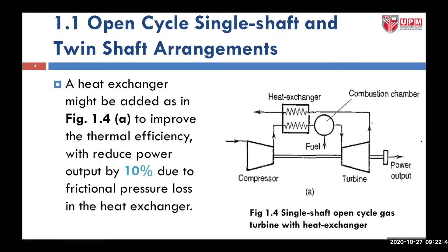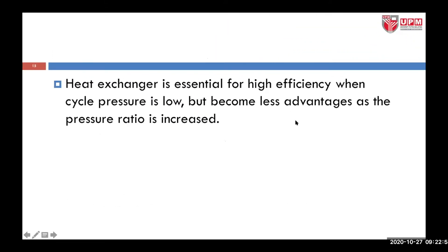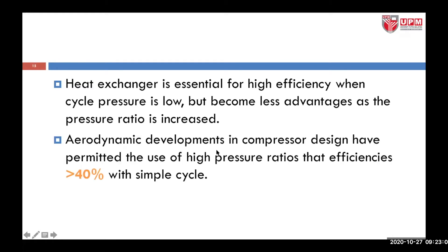This is an example of a single shaft where we have a single shaft connected to the compressor and the turbine — an open cycle with heat exchanger. A heat exchanger is essential for high efficiency when cycle pressure is low, but it becomes less advantageous as the pressure ratio increases in the compressor. Aerodynamic developments in compressor design have permitted the use of high pressure ratios, giving efficiency of more than 40% compared to a simple cycle.